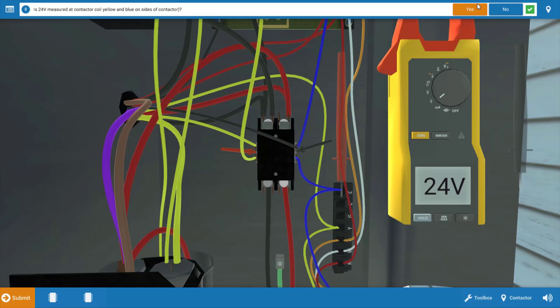So the contactor appears to be the source of the problem. But we're going to click yes on the procedure guide that we've measured 24, and we want to check the position of the contacts now.